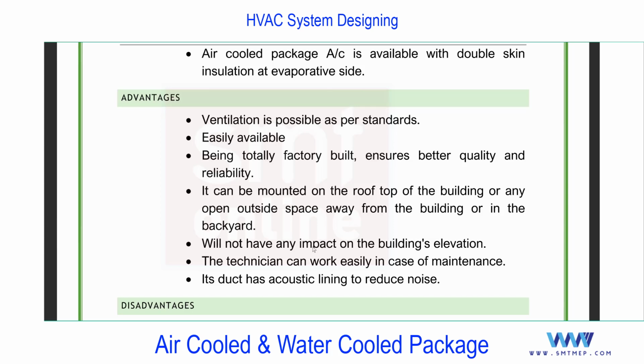So most of the points are related to air cooled because commonly in the market you'll find air cooled package, and it will not affect the building elevation because we are not placing it on the wall like a split system. We are placing it on a dedicated area on the roof or a separate space at the backside of the building. And in case of maintenance, the technician can work easily because it is not wall hung, and the ducts have acoustic lining to reduce the noise.